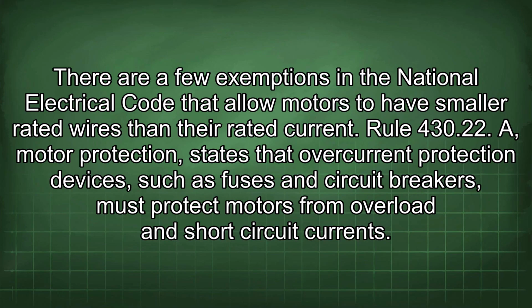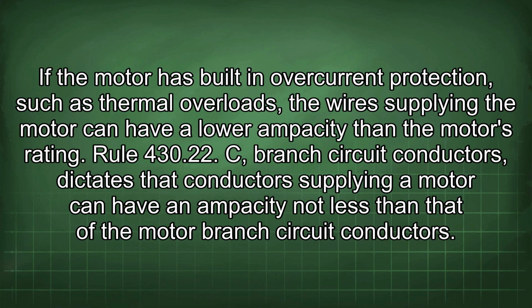There are a few exemptions in the National Electrical Code that allow motors to have smaller rated wires than their rated current. Rule 430.22 A, Motor protection, states that overcurrent protection devices, such as fuses and circuit breakers, must protect motors from overload and short-circuit currents. If the motor has built-in overcurrent protection, such as thermal overloads, the wires supplying the motor can have a lower ampacity than the motor's rating.